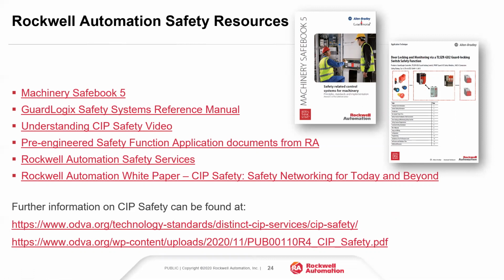And Rockwell also has over 75 pre-engineered safety functions, including ones with the Compact GuardLogix or GuardLogix in them, which provide a safety function showing the safety inputs, the logic device, and the output device, with sample code and things like that to help speed up your safety design and commissioning. And then Rockwell also has a nice white paper that talks about CIP safety over the network, and about the safety protocol and how it's safe.